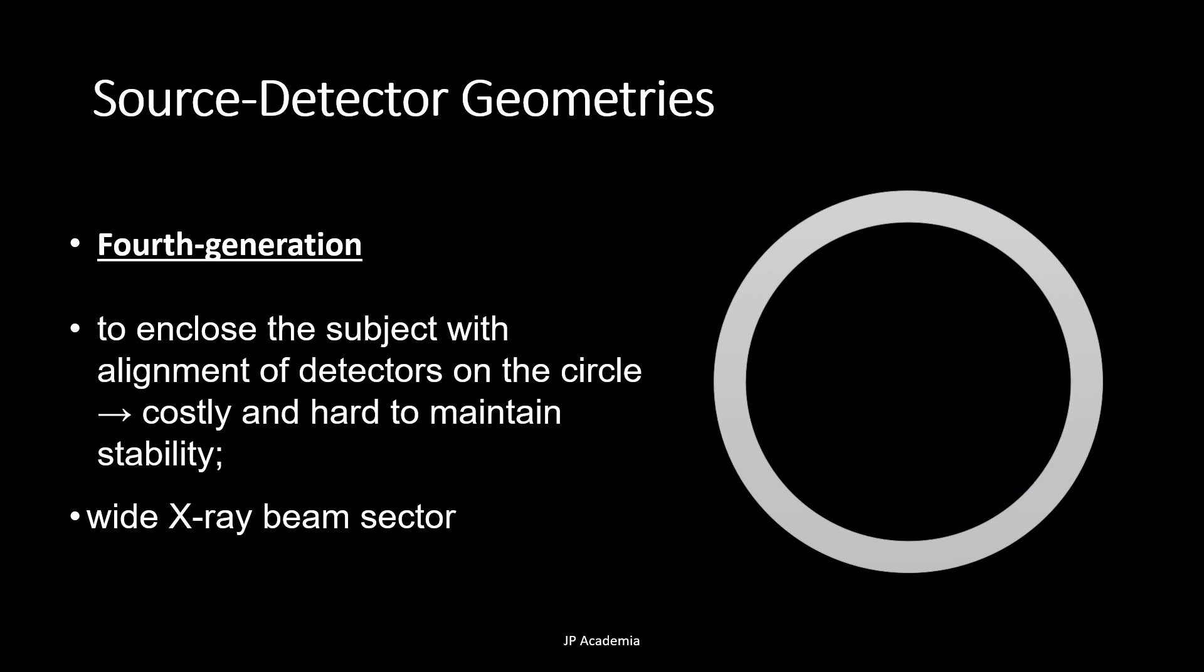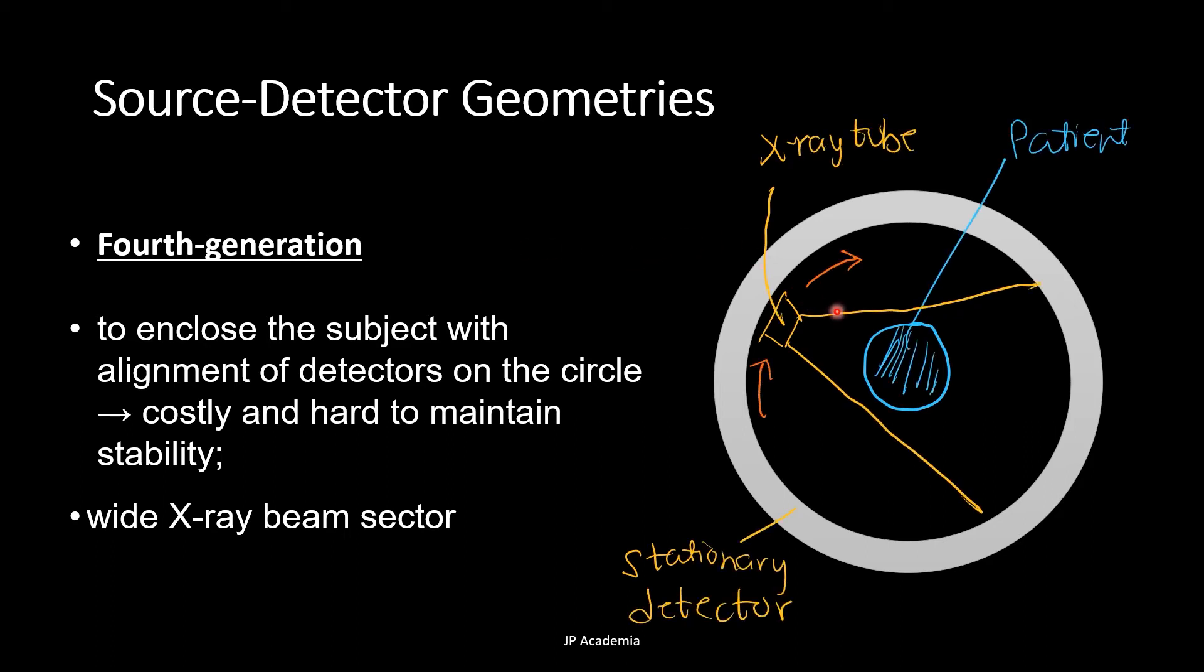For this lecture, this is the last generation that I will present, so the fourth generation. It has a rotating X-ray source, and a continuous 360 degrees ring of detectors. And a rotating only of the X-ray tube is observed, thus it reduces the time for scanning, and it has a stabilized composition.